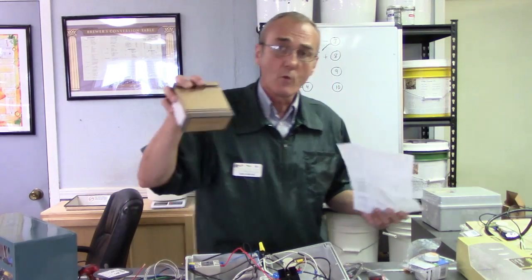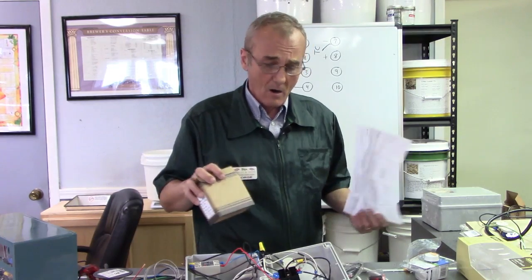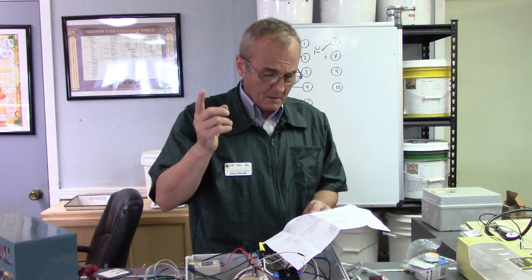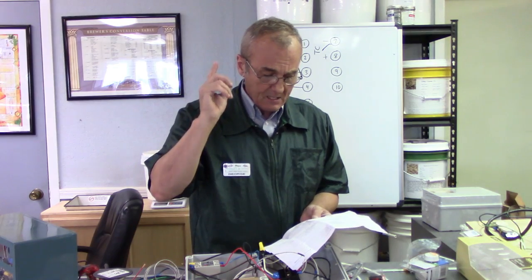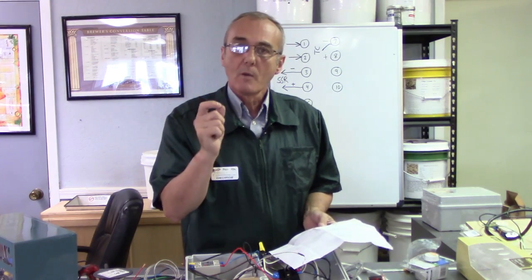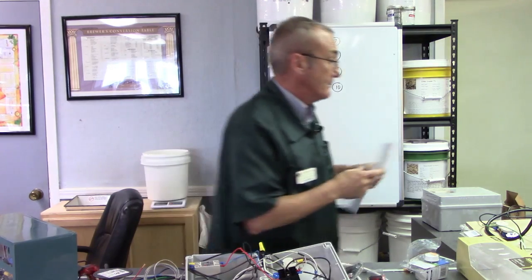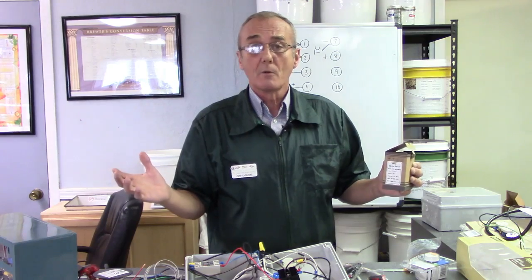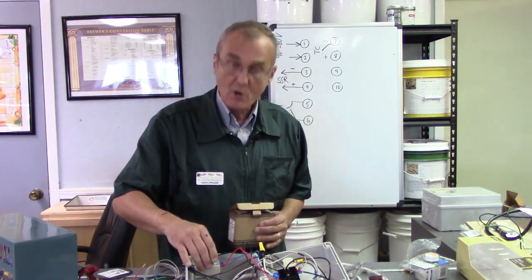There is a TD4 SNR, and I had a couple of TD4 RNRs. I had to do a little bit more research. The instructions are kind of complicated, you've got to read them four or five times and do a little bit of research. The real difference is the one we want is an SNR. The S represents a solid state relay logic, that's how it operates, it's an output. The N represents none, and the R represents a relay. So it's an SNR. An RNR is a relay, none, and a relay, which would have been internal. We know because of the power demand, using the internal relay on a PID is not going to help us because it will not withstand the power surge. So we use the external relay, and that's why we need an SNR.